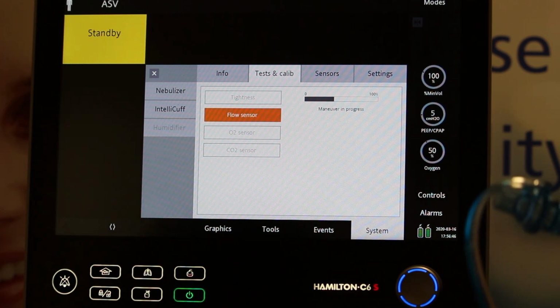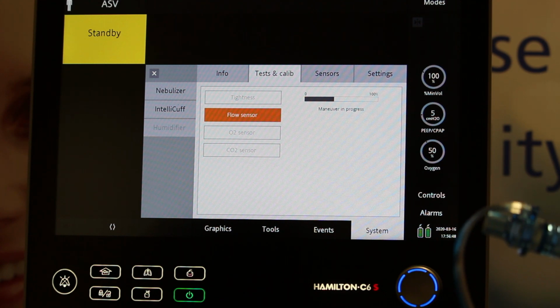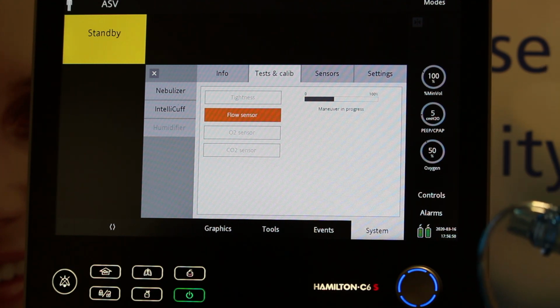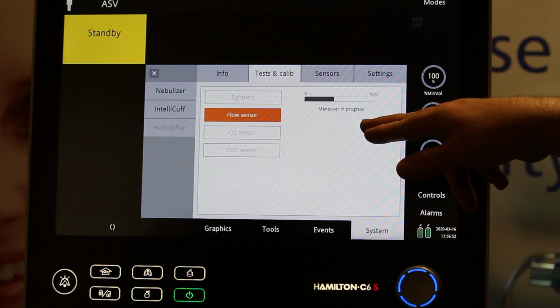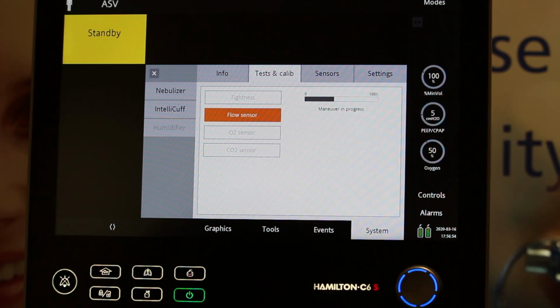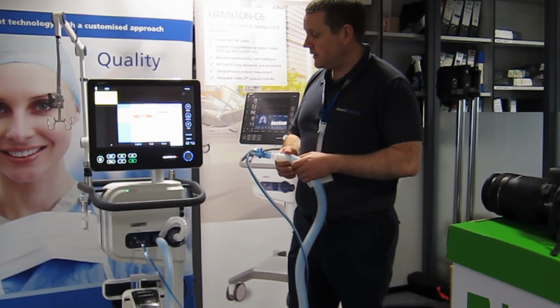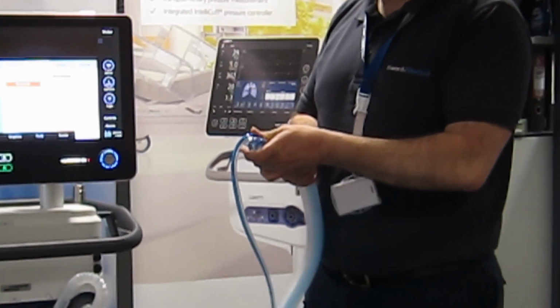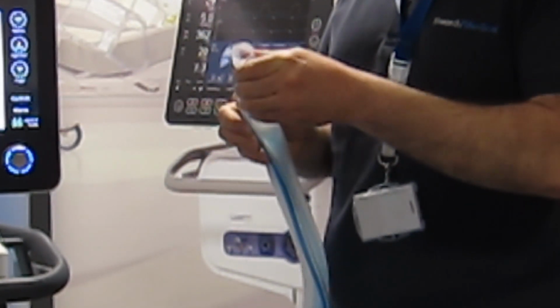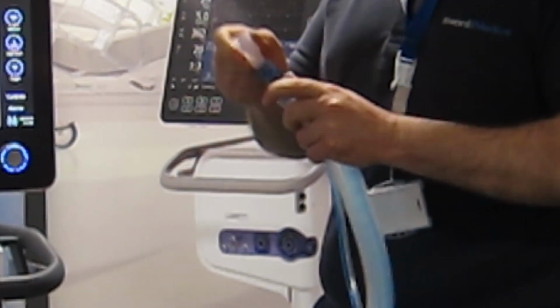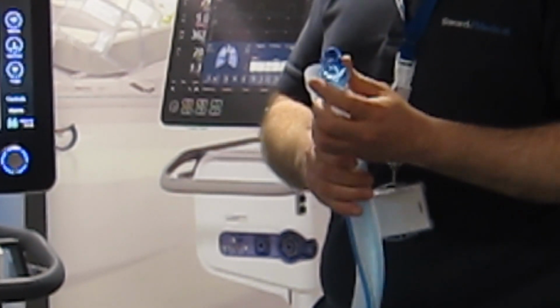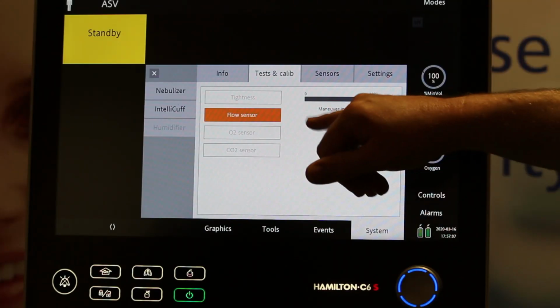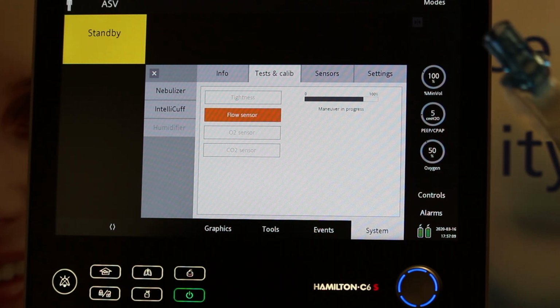I only get about 15 seconds from the time of the prompt to actually do the manoeuvre. So you must pay attention to the prompts on the screen. And as soon as it prompts you to do the manoeuvre, I've only 15 seconds from that point. So I unplug my flow sensor, turn it around to the normal position, mounting my sizing adapter back on the sensor, and now it says manoeuvre in progress, so it's doing the same calibration in the opposite direction.